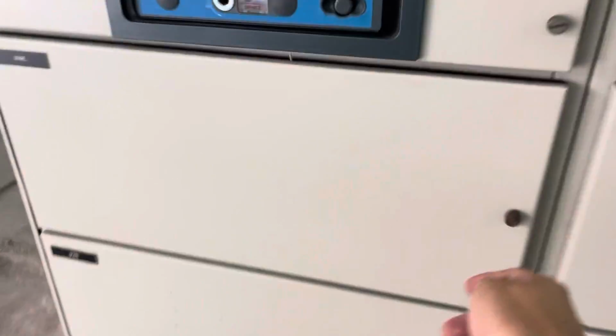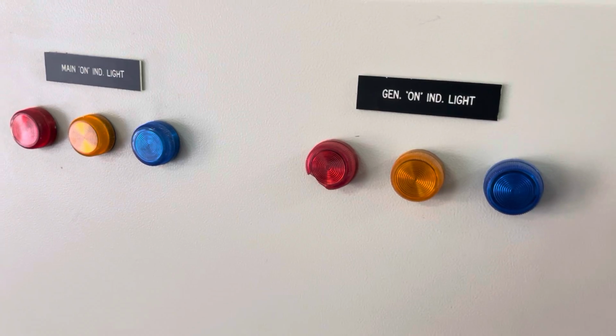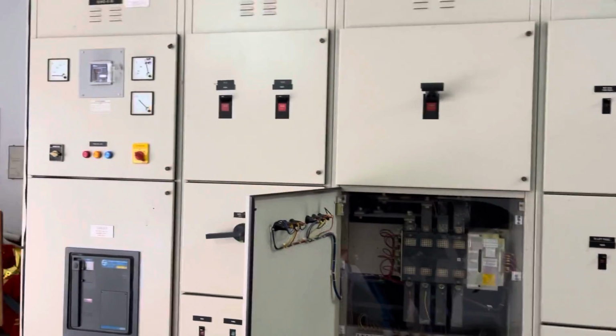ACB. This MSP panel, there's no surge arrestor installed. I propose one because according to Malaysian standard, now all LV main switchboards must install surge arrestor. Okay. This is the ATS panel. Indicator light faded. Advised to replace. Okay. Here we have it.